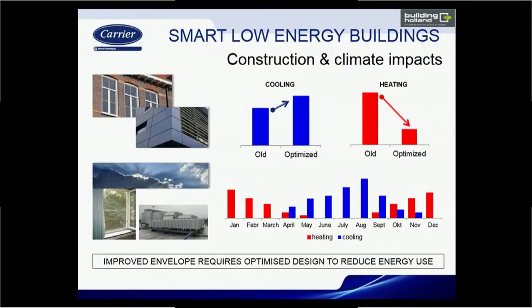Because in fact, when you insulate the building too much, the internal gains, the heat that's generated, can't escape. Since it can't escape in a more traditional way, we have to provide more cooling for a given situation. But at the same time, because that heat can't escape, the heating loads improve.